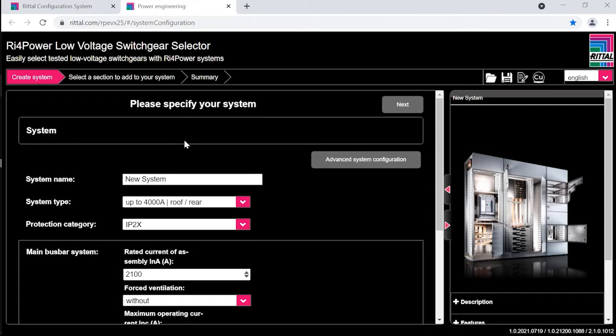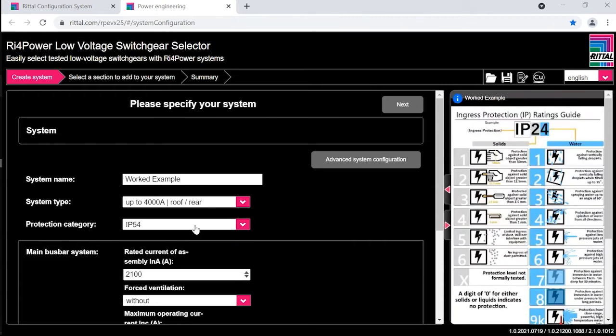Being online, as I said previously, it's very quick and interactive as well. It'll give you options to change titles or drop down boxes, which makes life a little bit easier. So the title will be worked example. It is 4,000 amps up to, so our rating is 1200 amps or so. That's okay. For the IP rating, we'll go for IP64. As I said previously, for this configurator to work we need some information: the dimensions and specification of the customer, etc.